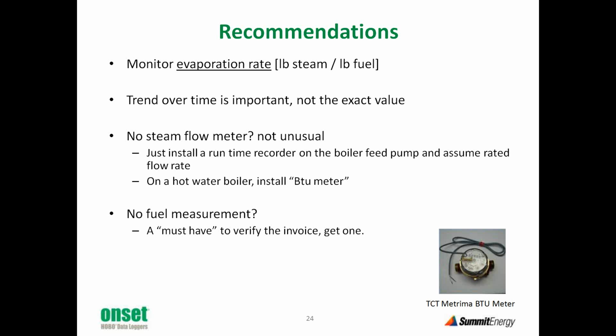If it's a hot water boiler, you're not evaporating at all. You may need a BTU meter, which is just a fancy way of saying we're going to measure water flow and we're going to measure temperature difference, temperature in and temperature out, and use that to calculate the BTUs.